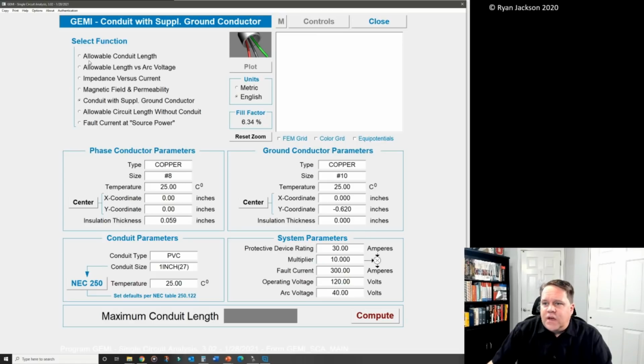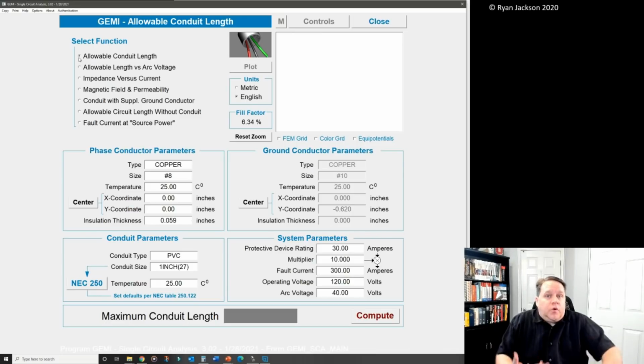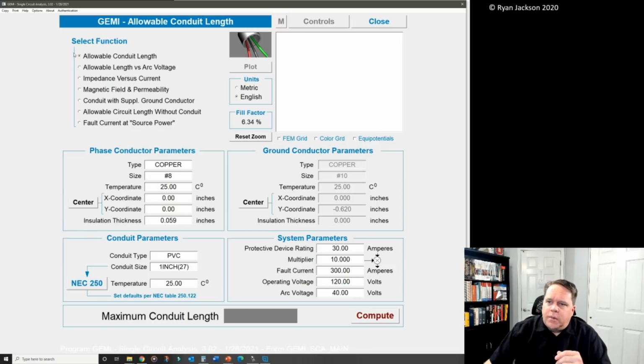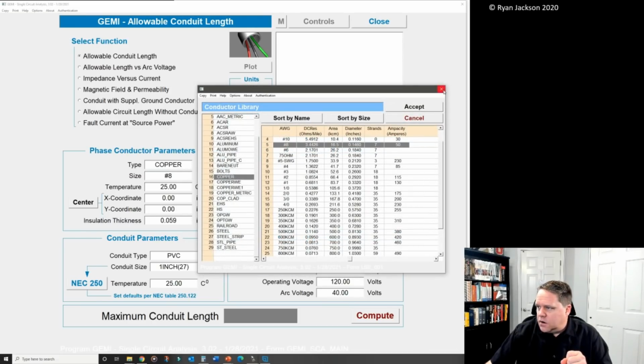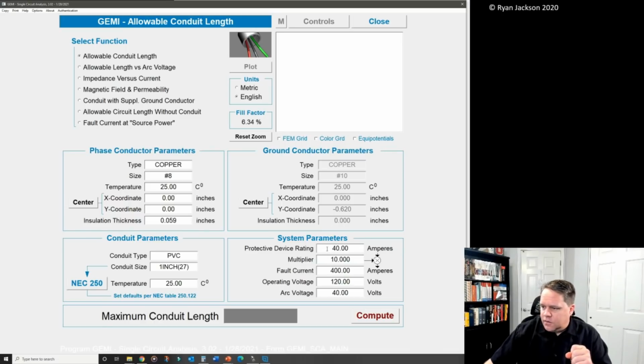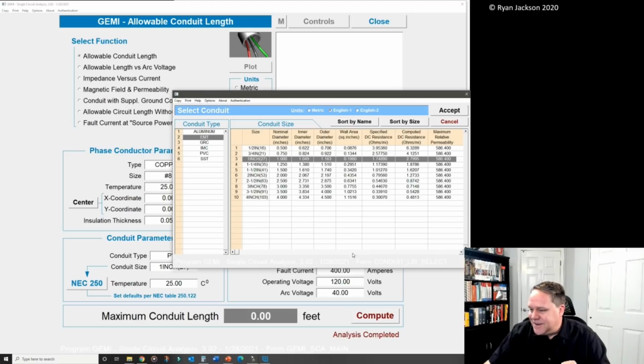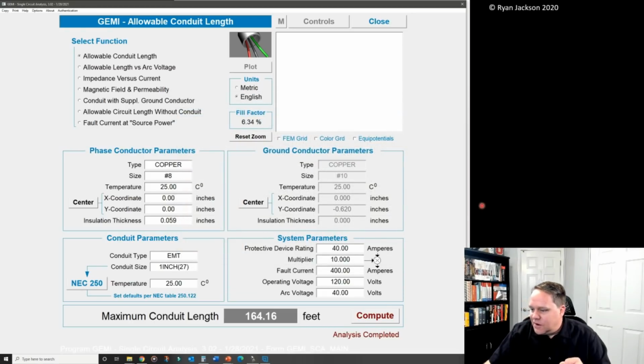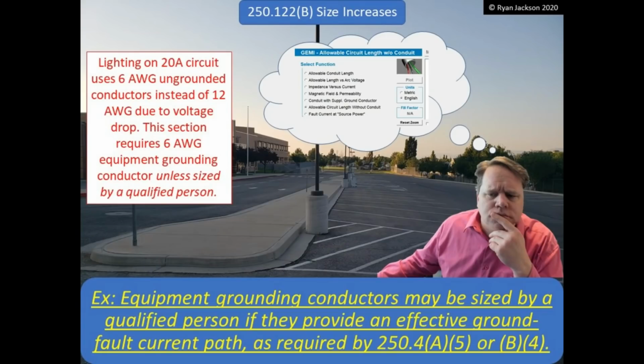We can do some other things as well using the same software. What if I'm using just a metal conduit as my equipment grounding conductor? What if I'm just using EMT? No green wire in it. That's legal, right? Assuming we're not doing a swimming pool or healthcare, things like that. But how far can you run a piece of EMT before it has so much resistance that it will no longer be able to trip a breaker? I mean, different concept than the increasing in size thing that we were discussing, but kind of the same principle. We can calculate that. So up here is the allowable conduit length. If I'm running 8 gauge conductors and I've got a 40 amp circuit breaker, I could calculate. Let's see here. Conduit is not going to be PVC, is it? EMT, and we'll use 1 inch for that. I could run that 164 feet before I'd have to concern myself with running an equipment grounding conductor inside of it.